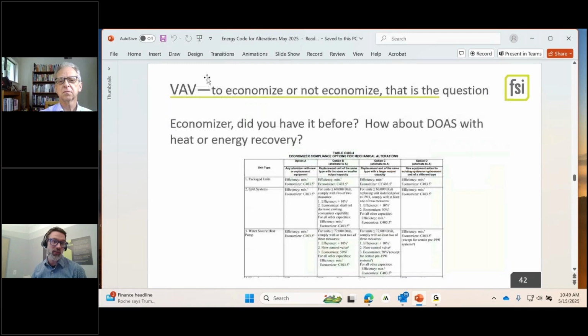If you do not have a DOAS requirement, you get to keep doing old school economizer, like back in the day, like what I started my career doing. And Duane already mentioned this giant table, and it really matters. Did you have an economizer, an ability to move 100% of your air through your unit from outside air so that you can use free cooling? I put that in air quotes because you're still paying fan energy, but free cooling or not. And there can be air balancing questions, particularly on big buildings with built up air handlers. It can be impossible, and you're trying to do one of these other options to get yourself there. Next one.